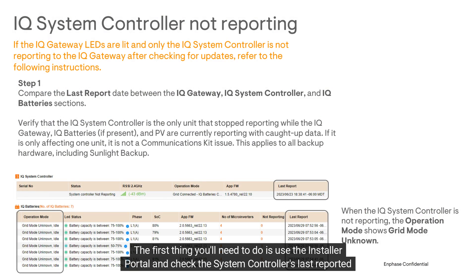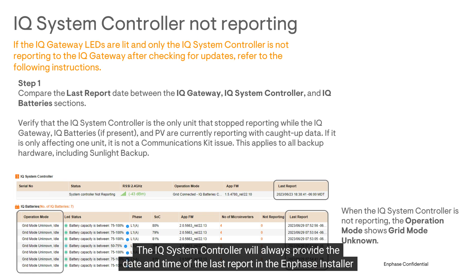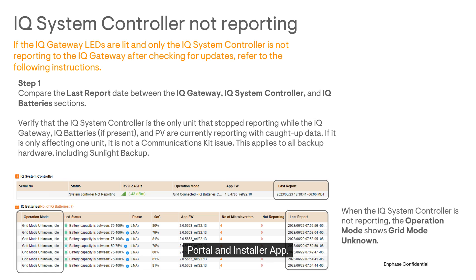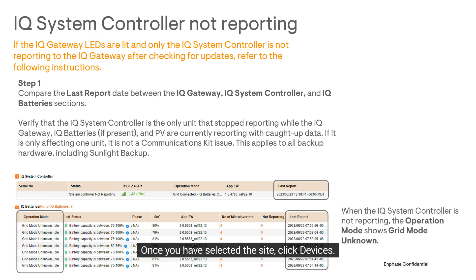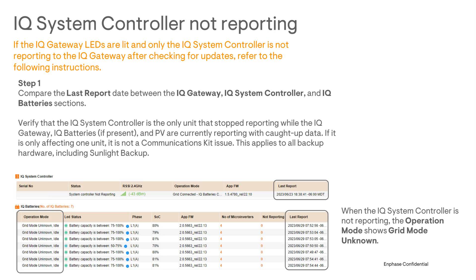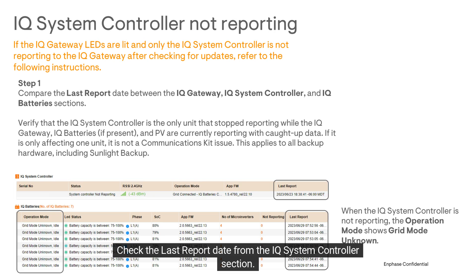The first thing you'll need to do is use the installer portal and check the system controller's last reported timestamp. The IQ system controller will always provide the date and time of the last report in the Enphase installer portal and installer app. To view this information in the Enphase installer portal, log in and search for the affected site. Once you have selected the site, click Devices. Check the last report date from the IQ system controller section.